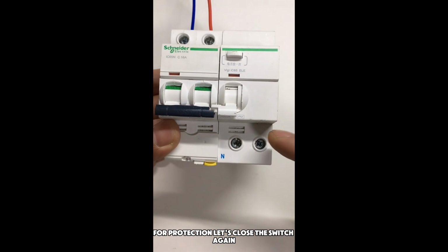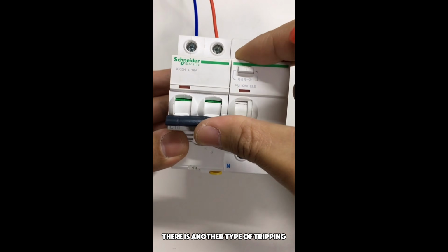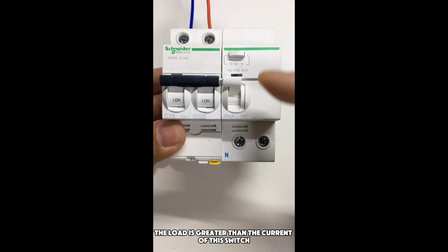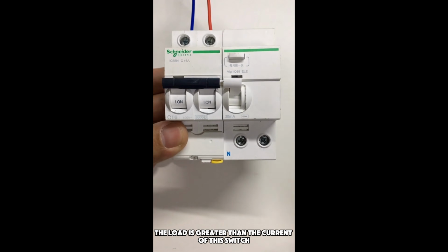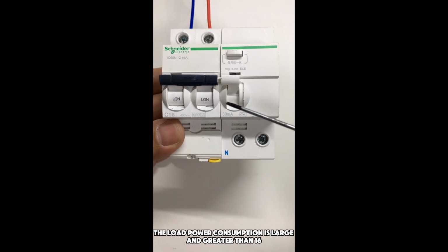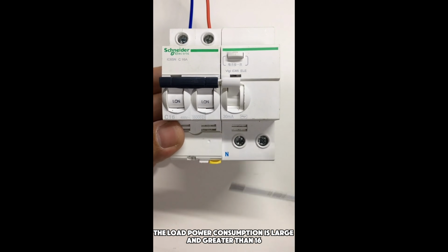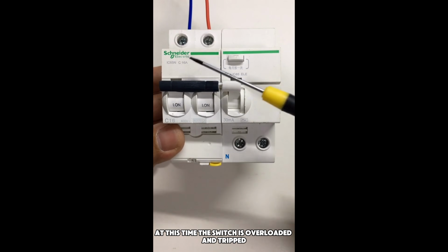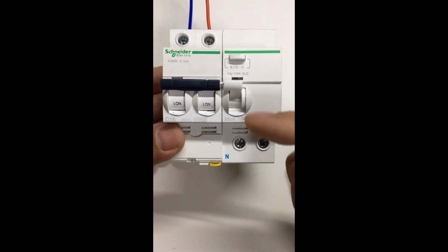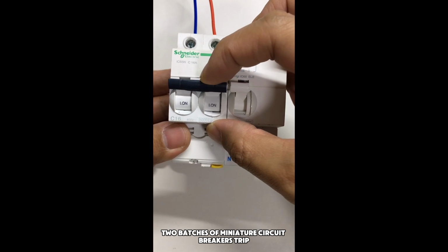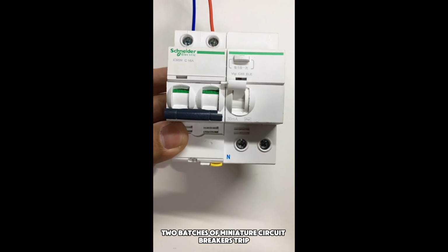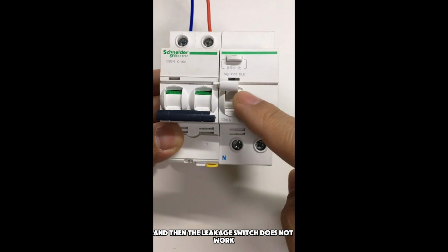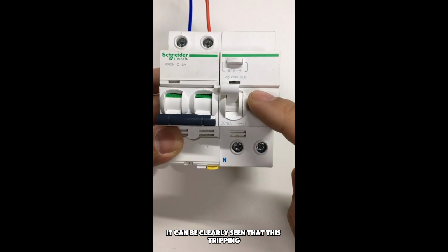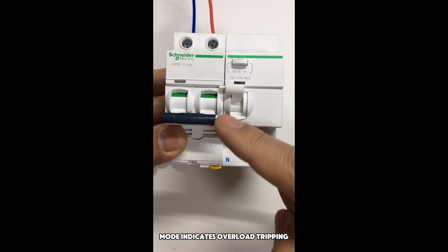Let's close the switch again. There is another type of tripping. For example, the load is greater than the current of this switch. The load power consumption is large and greater than 16. At this time, the switch is overloaded and tripped. How does it trip? The 2-pole miniature circuit breaker trips, and then the leakage switch does not work. It can be clearly seen that this tripping mode indicates overload tripping.